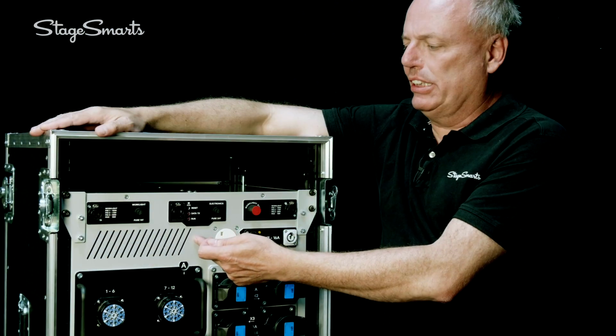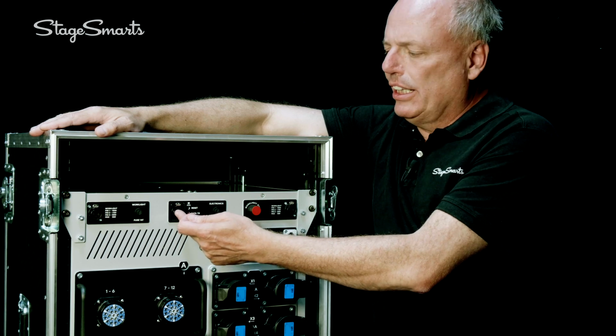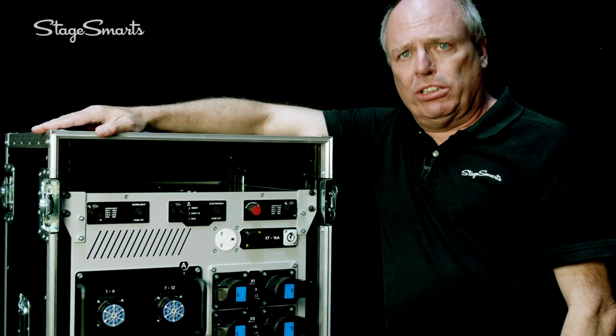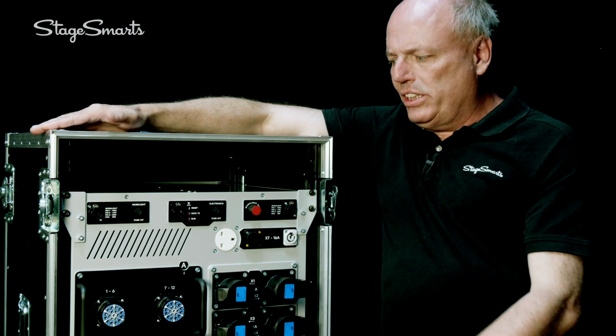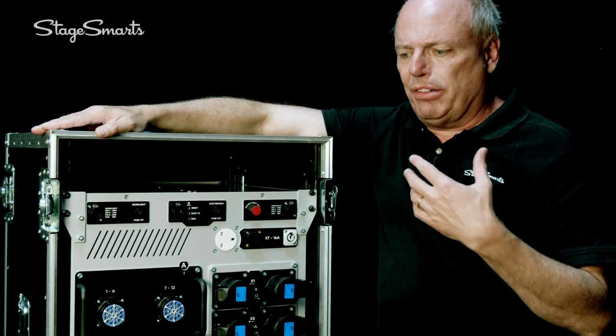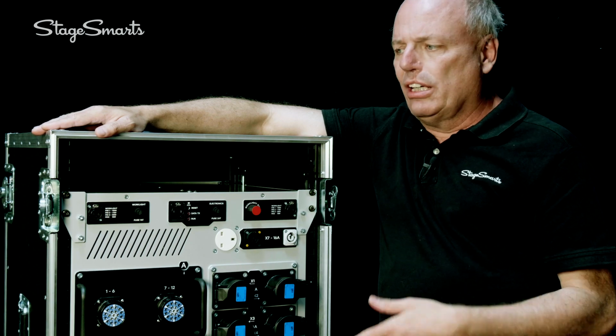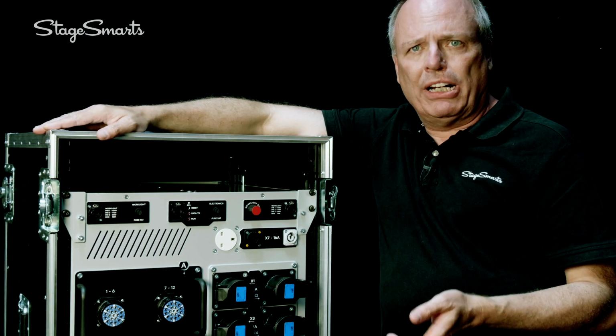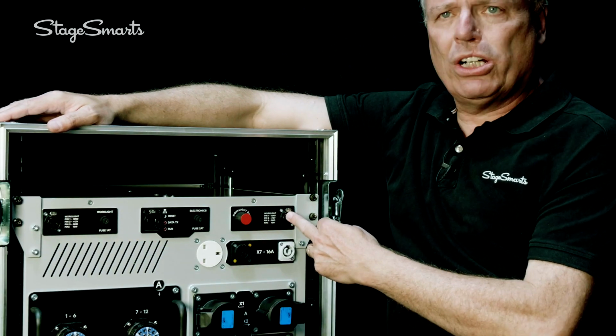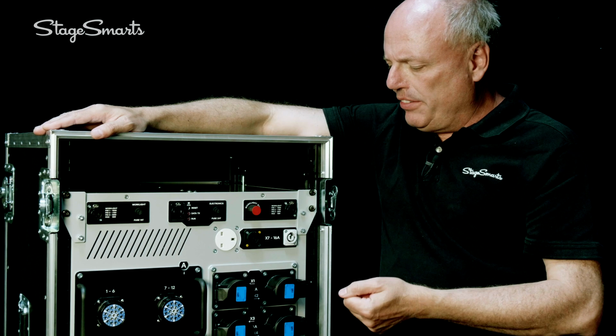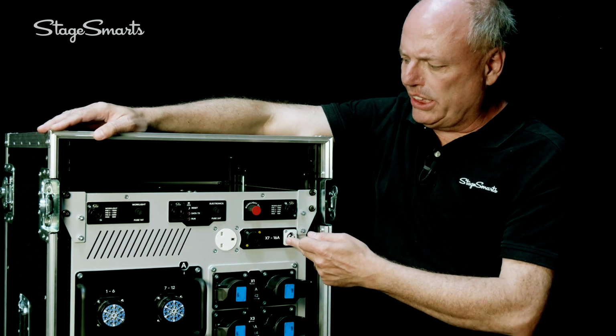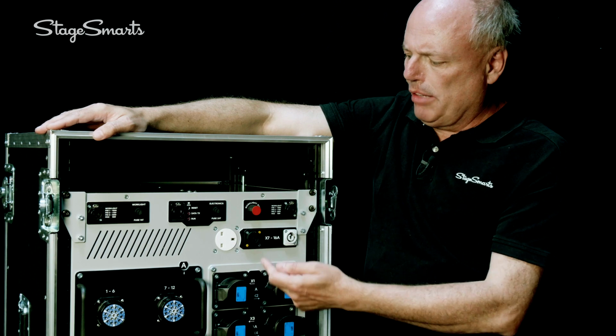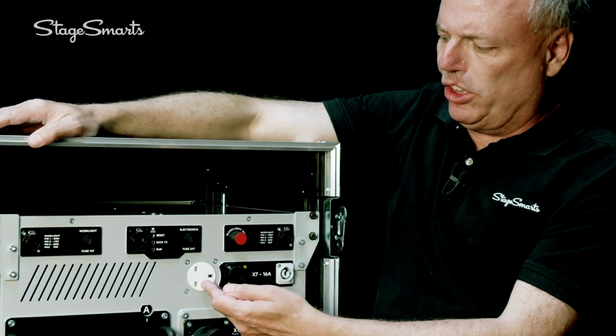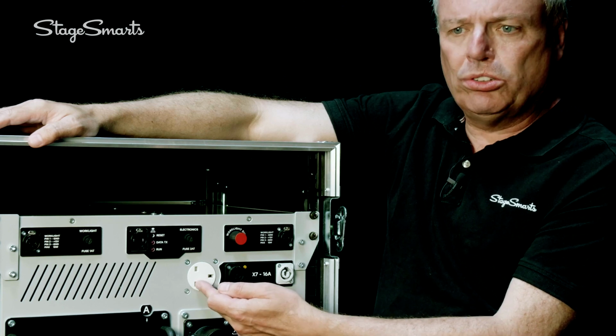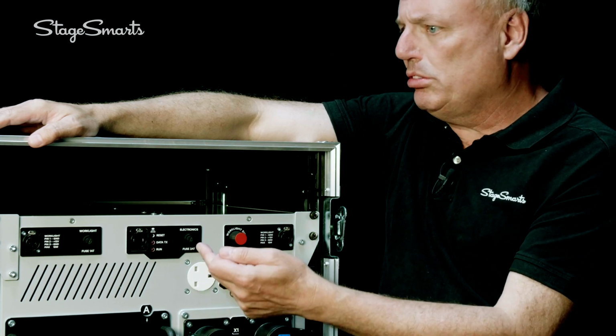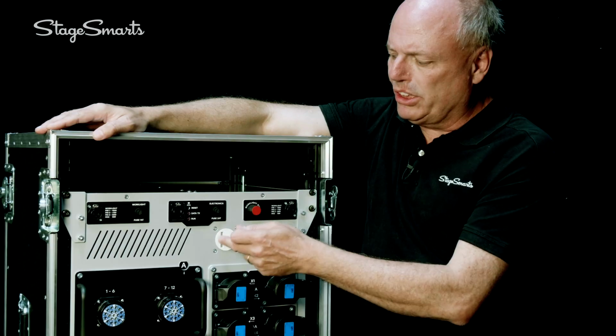At the center of the back of the Smart PDU, we have our network connection. The network connection connects to the internal server. The internal server takes in all the data about the load connections, the incoming power, voltage, current, etc., and presents that on any device that has a web browser. We have two sockets for work lights with adjustable brightness. We have a set of utility sockets. In this case, we have a 15 amp UK socket, a PowerCon True1, and a regular PowerCon. This particular connection is also available as a Schuko, German Schuko, Swiss connection, Australian connection, anything you want. So it's selectable by country.